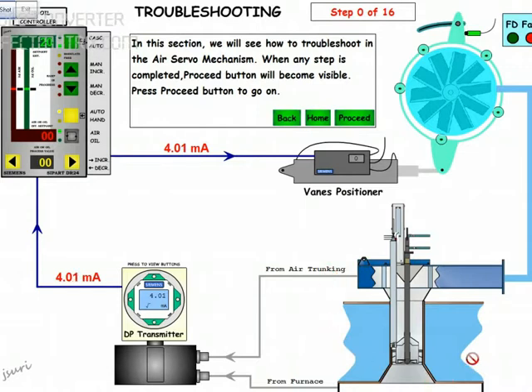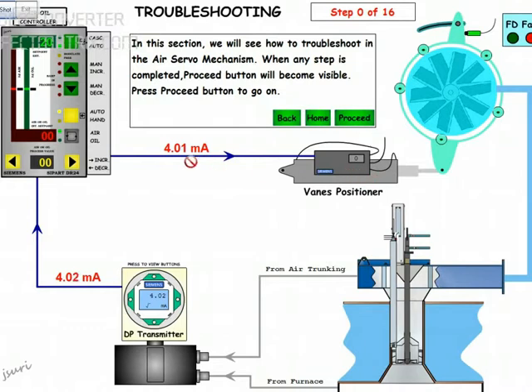This is the boiler. You can see one line coming — the air trunking line — to the DP transmitter, and one from the furnace. The signal from the DP transmitter goes to the air oil controller and then to the vanes positioner, which pushes the positioner to increase or decrease the flow to the boiler as per the load.